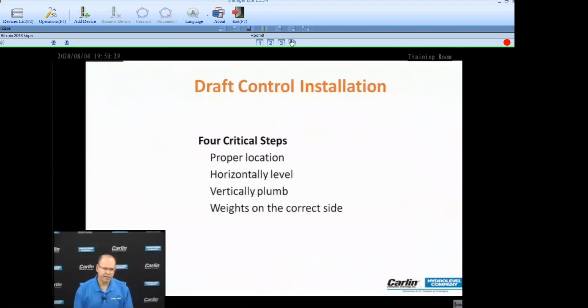You look at a device that's installed correctly. So is it in the right location? Is it plumb? Is it vertical? Are the weights correct on the damper? Are they on the correct side? Some of them depend on whether it's horizontal or vertical. Are the weights even there? What did you do when you added the weights or adjusted the weight and you turned it? What were you trying to achieve? Were you taking a draft test at the time?